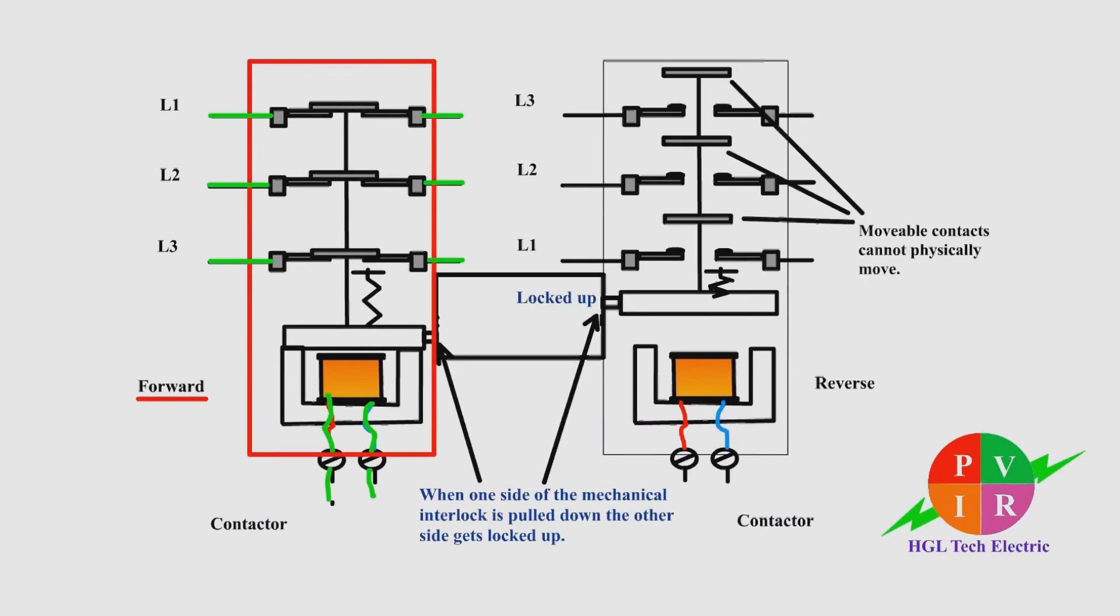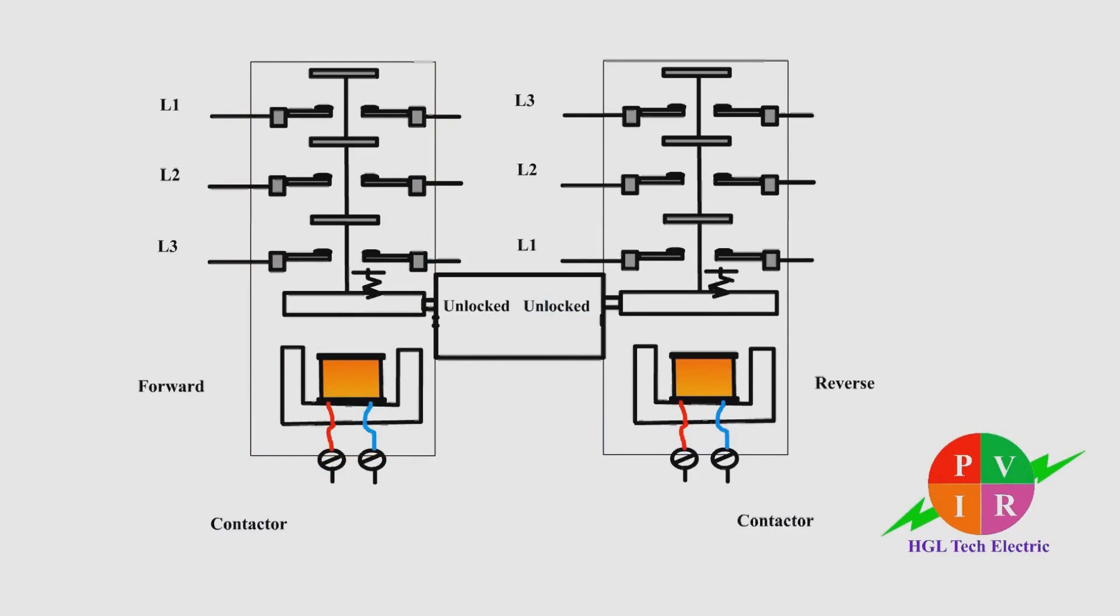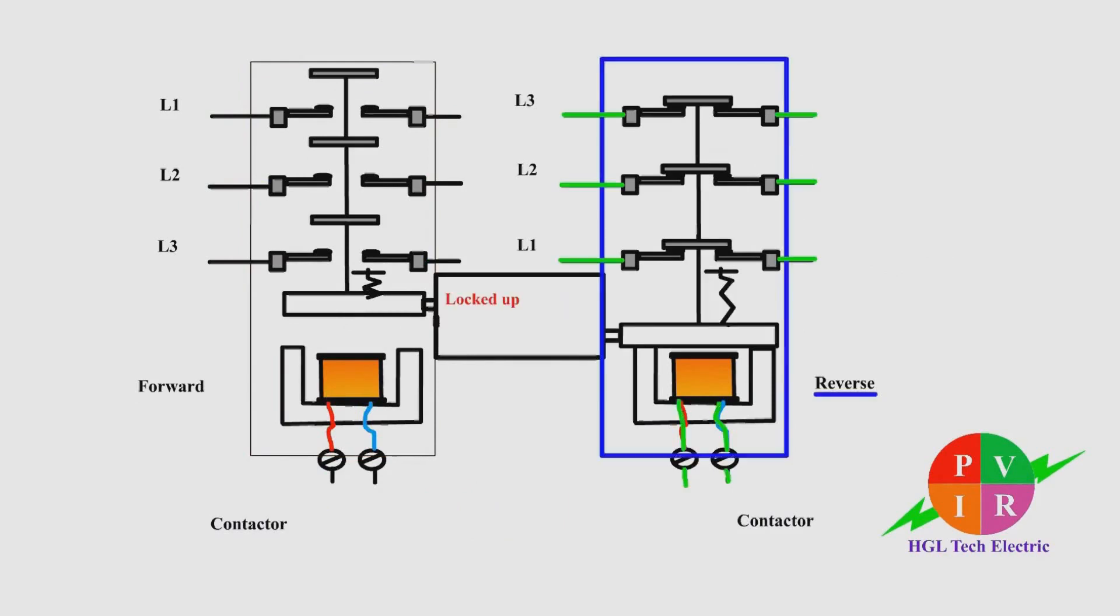When the movable contacts of the energized contactor pull down one side of the mechanical interlock, the other side gets locked up.